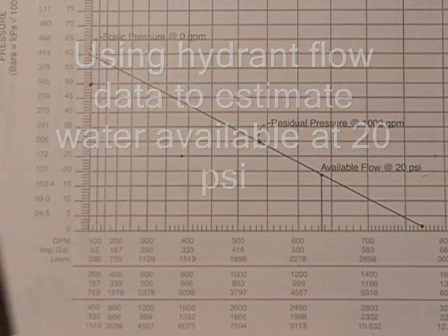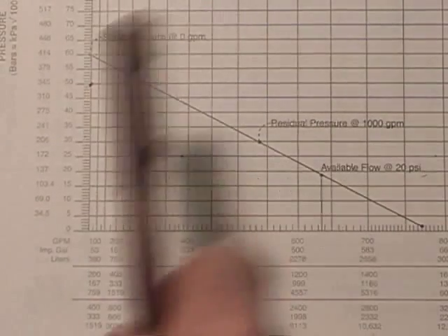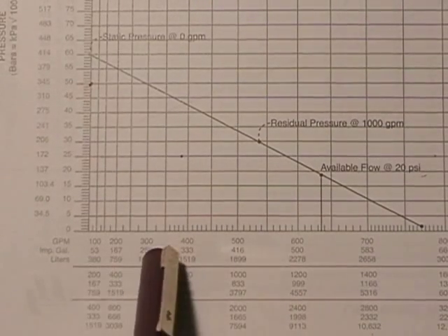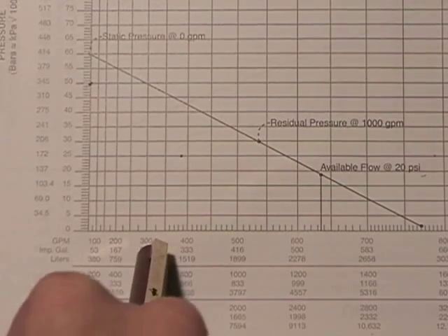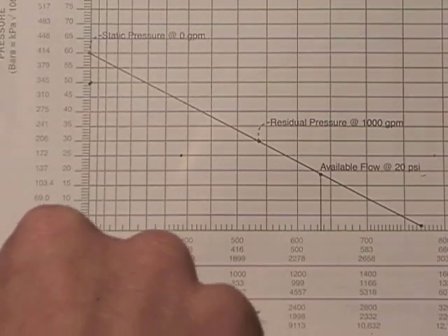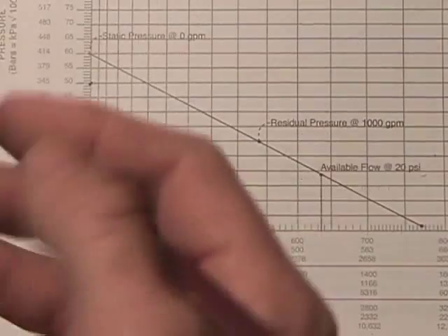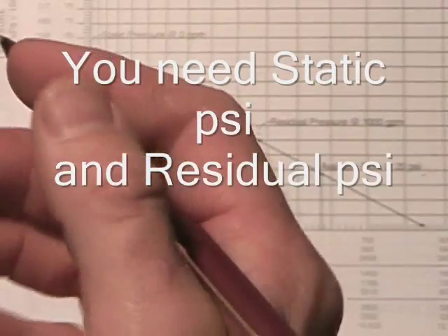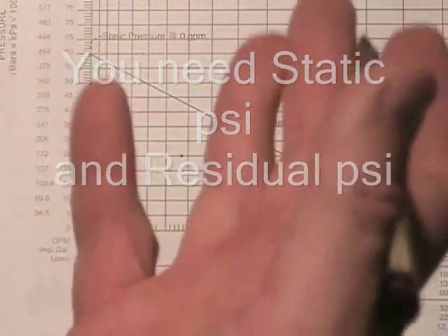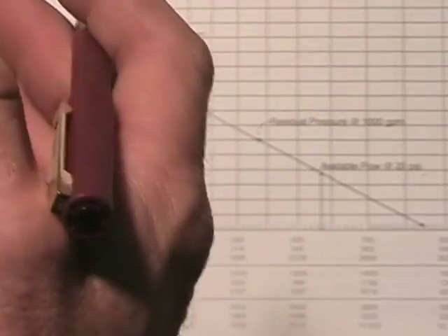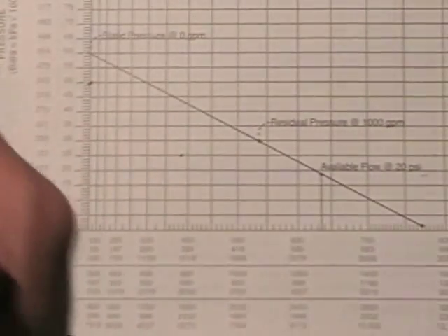During hydrant flow testing, many times we'll use this universal water flow chart. What it's going to do is tell us how many gallons a minute are available at 20 psi. Remember that when we calculate how many gallons a minute are available from a hydrant, we start off with a static and then a residual test after we're flowing another hydrant to see how far it drops.